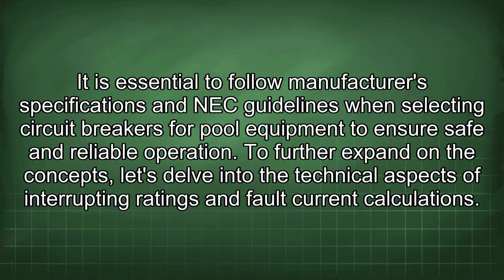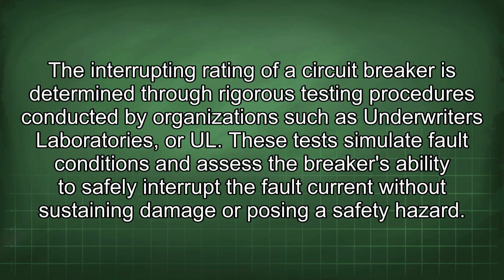It is essential to follow manufacturers' specifications and NEC guidelines when selecting circuit breakers for pool equipment to ensure safe and reliable operation. To further expand on the concepts, let's delve into the technical aspects of interrupting ratings and fault current calculations. The interrupting rating of a circuit breaker is determined through rigorous testing procedures conducted by organizations such as Underwriters Laboratories, or UL. These tests simulate fault conditions and assess the breaker's ability to safely interrupt the fault current without sustaining damage or posing a safety hazard.